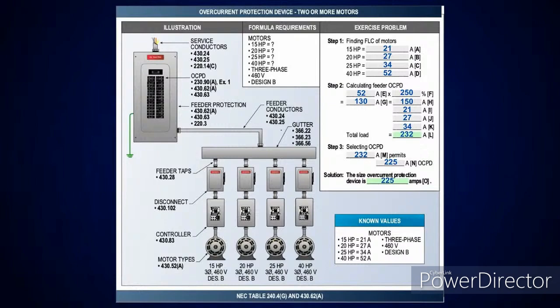Then you're going to go look at table 430.52C1. You'll pick up for an inverse time circuit breaker is what we're sizing here. And you come across, it'll tell you take it at 250%. And then you take that 250%, that gives you 130 amps, and go up to the next standard size, which is a 150 amp overcurrent device. Add the other 3 motors together, gives you 232 amps. Then you drop down, which would be a 225 amp overcurrent device. Okay? Right. So hopefully everybody that's been doing their homework got all these right.